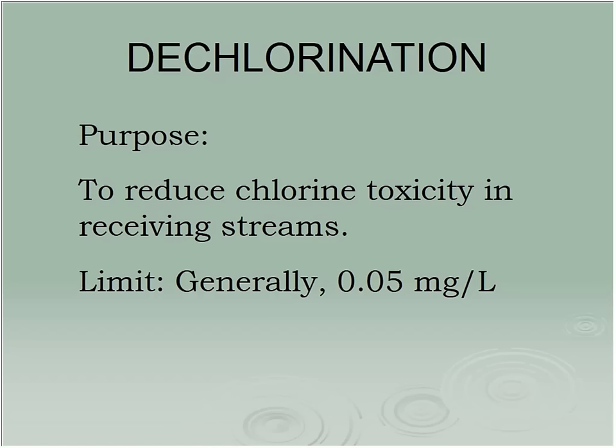So, again, chlorine was cheap, so they said, okay, we'll disinfect. They just throw in chlorine like crazy. So they had this huge residual going to the river. And the fish were turning white. So EPA said, oh, back off here. We're going to have to dechlorinate. We can't have that much residual chlorine going into the waters. So now we have to dechlorinate. You can have as much residual as you want for your safety factor, but you have to get rid of it before you can discharge.